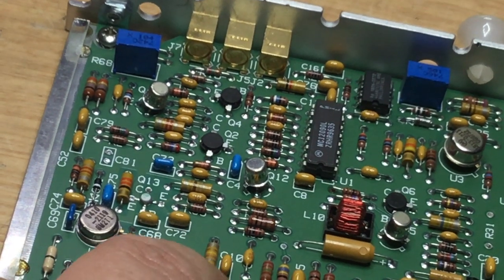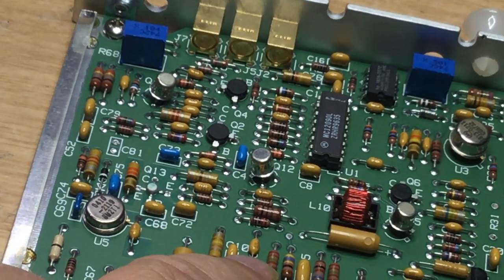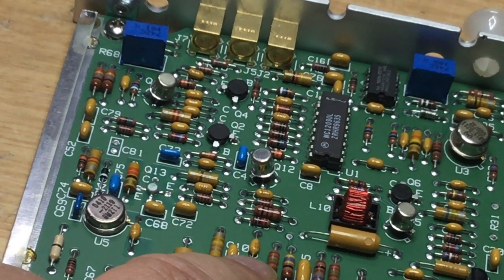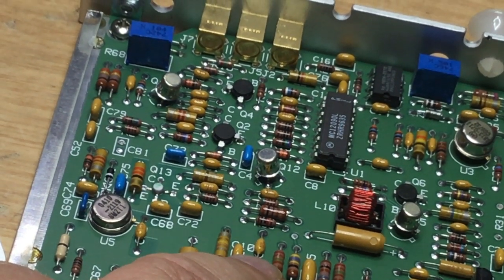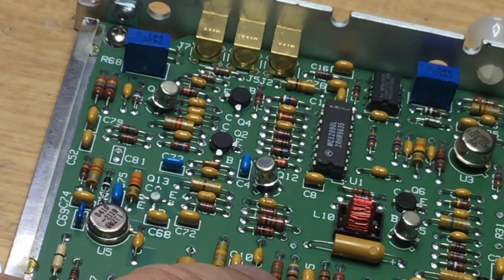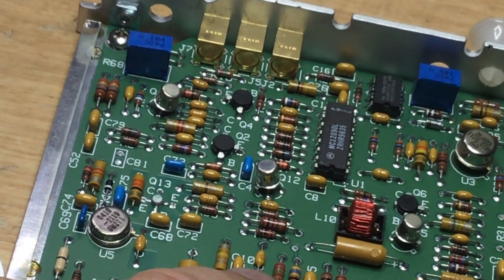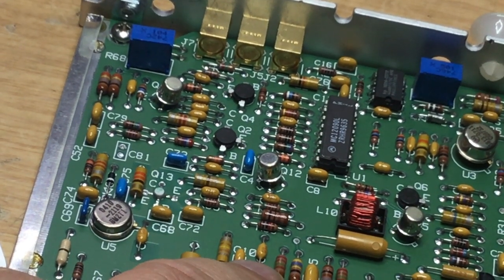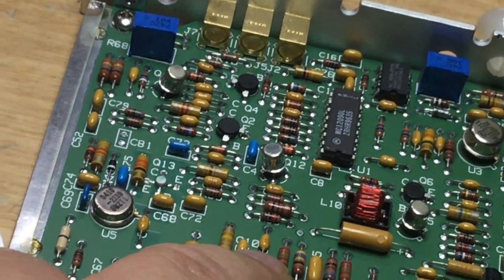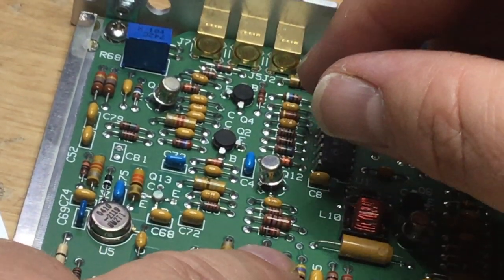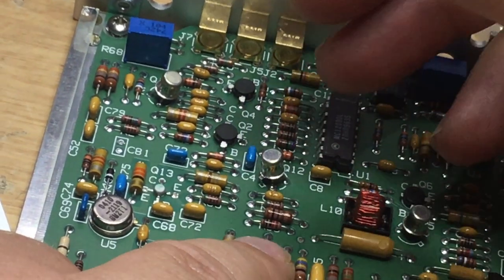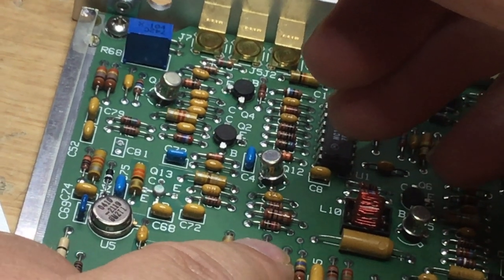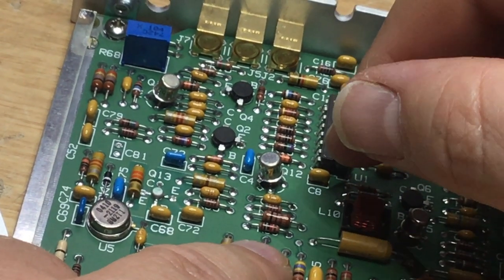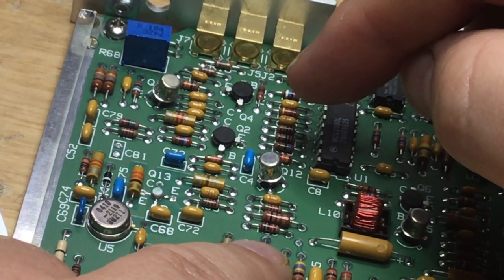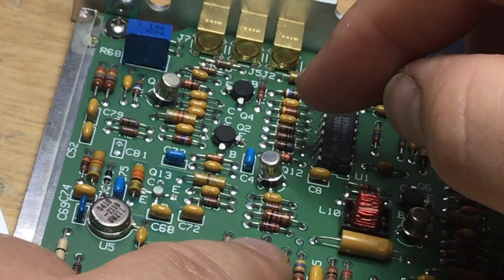It just shows in the block diagram for the third converter, the divider for the 600 megahertz signal to divide it down to 300 megahertz. So it's very, very interesting. It's obviously not got any influence over the tune, so we're displaying an image on the screen of the spectrum analyzer. The oscillator is running, as we proved. 600 megahertz is there. The 10 megahertz reference is also going to the phase comparator. It could be something like the buffer amp that sends a buffered amplified signal on the 300 megahertz output line to the phase comparator is not working.